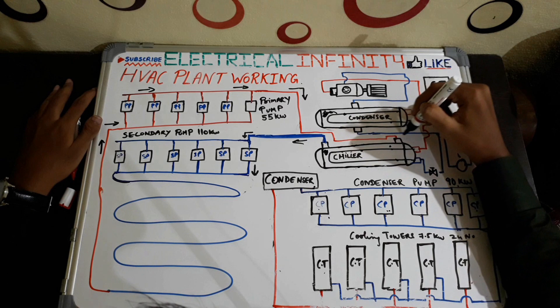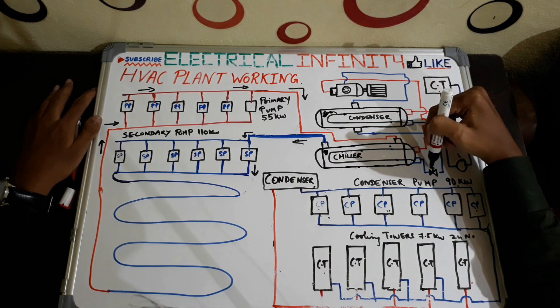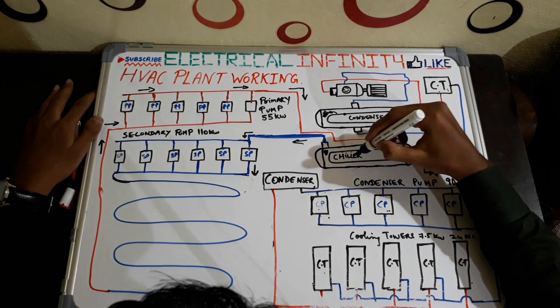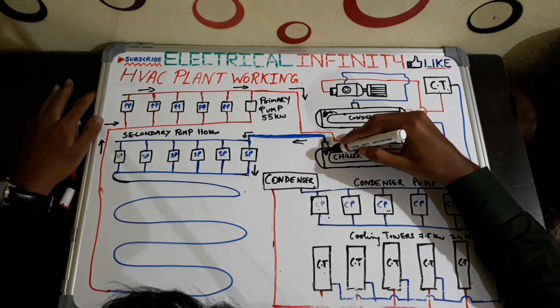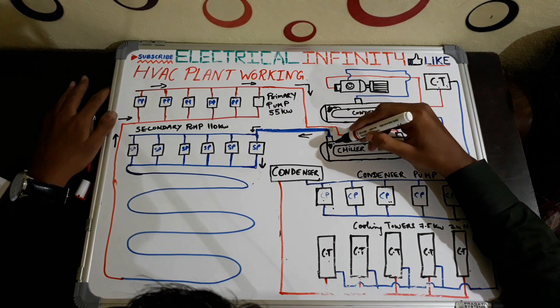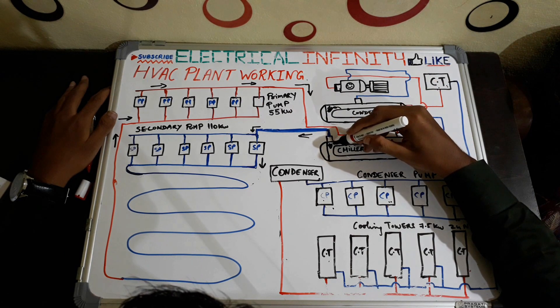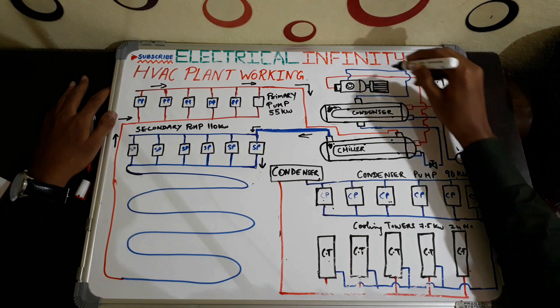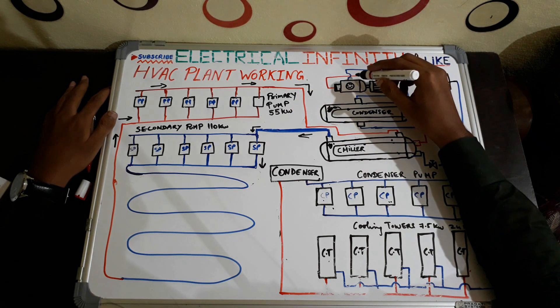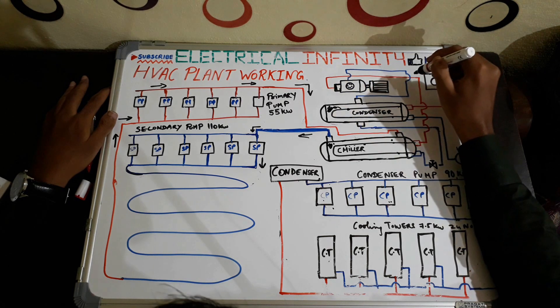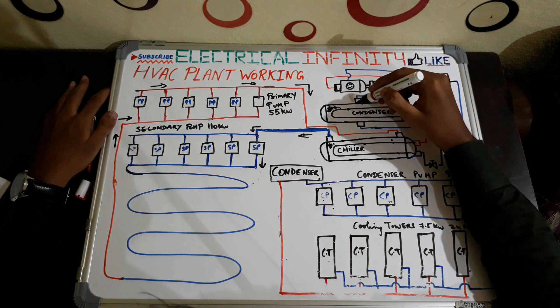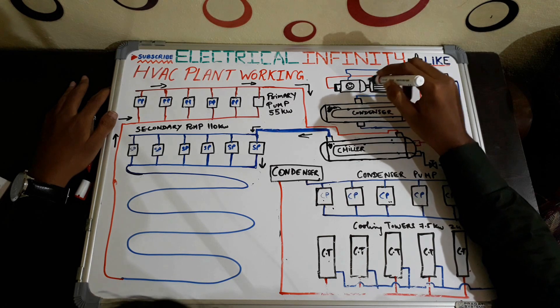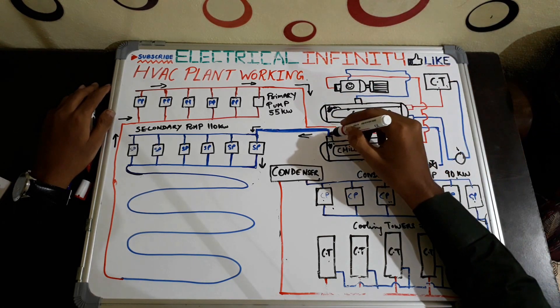After the refrigerant is cooled, it is sent to the chiller through the expansion valve, which decreases the pressure of the refrigerant. In the chiller, the cool refrigerant is in the tube type and the high-temperature water is in the shell type. Heat exchange takes place between the low-temperature refrigerant and the high-temperature water — the water gets cooled and the refrigerant gets heated. The heated refrigerant is transferred to the compressor, compressed, and the high-temperature, high-pressure refrigerant is sent back to the condenser.